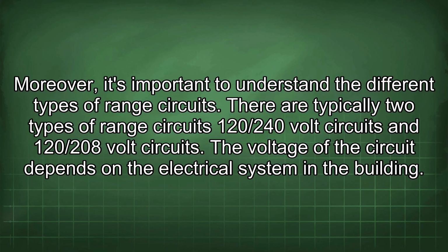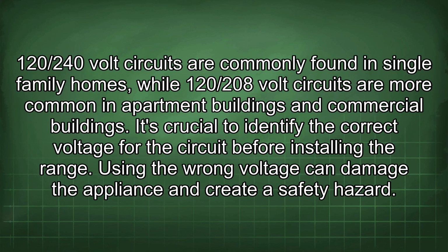Moreover, it's important to understand the different types of range circuits. There are typically two types of range circuits: 120/240 volt circuits and 120/208 volt circuits. The voltage of the circuit depends on the electrical system in the building. 120/240 volt circuits are commonly found in single-family homes, while 120/208 volt circuits are more common in apartment buildings and commercial buildings. It's crucial to identify the correct voltage for the circuit before installing the range. Using the wrong voltage can damage the appliance and create a safety hazard.